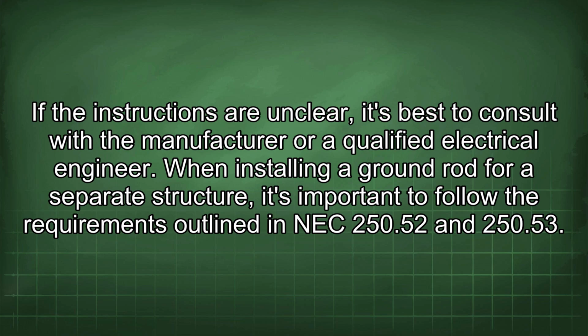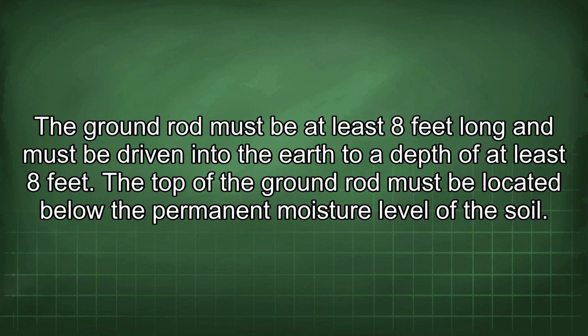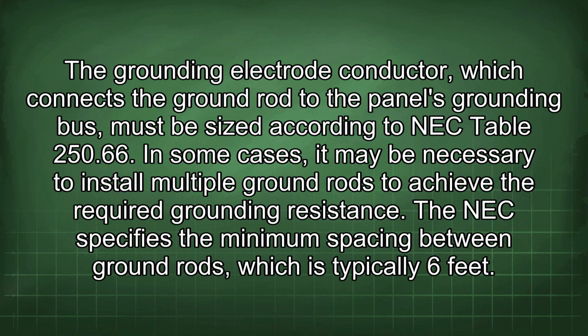When installing a ground rod for a separate structure, it's important to follow the requirements outlined in NEC 250.52 and 250.53. The ground rod must be at least 8 feet long and must be driven into the earth to a depth of at least 8 feet. The top of the ground rod must be located below the permanent moisture level of the soil. The grounding electrode conductor, which connects the ground rod to the panel's grounding bus, must be sized according to NEC Table 250.66. In some cases, it may be necessary to install multiple ground rods to achieve the required grounding resistance. The NEC specifies the minimum spacing between ground rods, which is typically 6 feet.